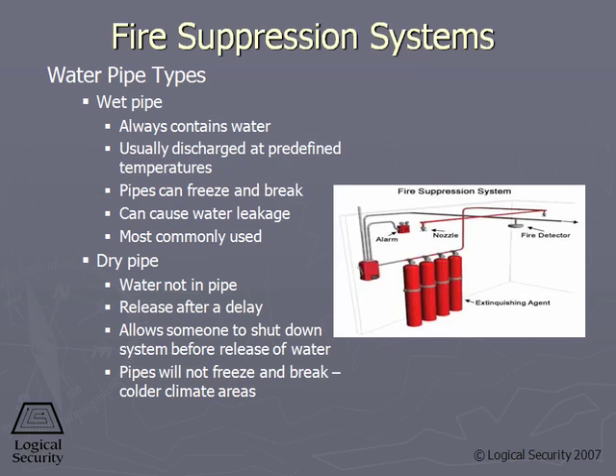Next, we're going to look at sprinkler systems. There are four types of sprinkler systems that you need to know for the CISSP certification exam. The first type of sprinkler system is called the wet pipe. Now, the wet pipe sprinkler system is where the water flows all the way up to the discharge head, generally located in the ceiling. And the problem with this is if the area is not thermally controlled, the water in these pipes can freeze and break.